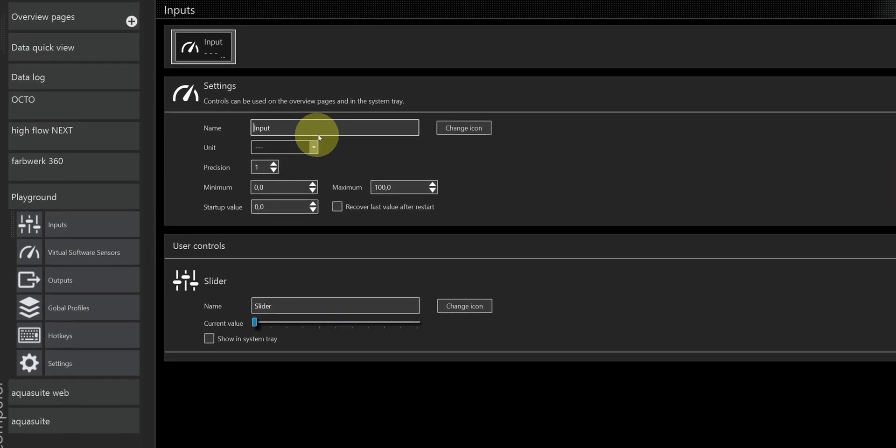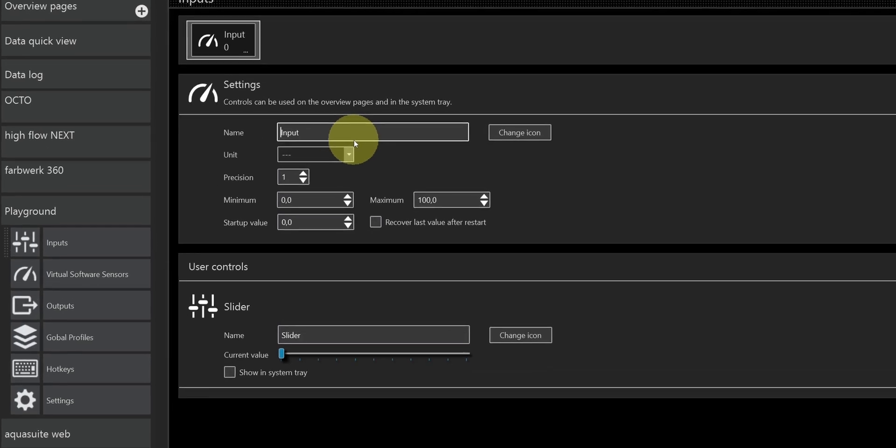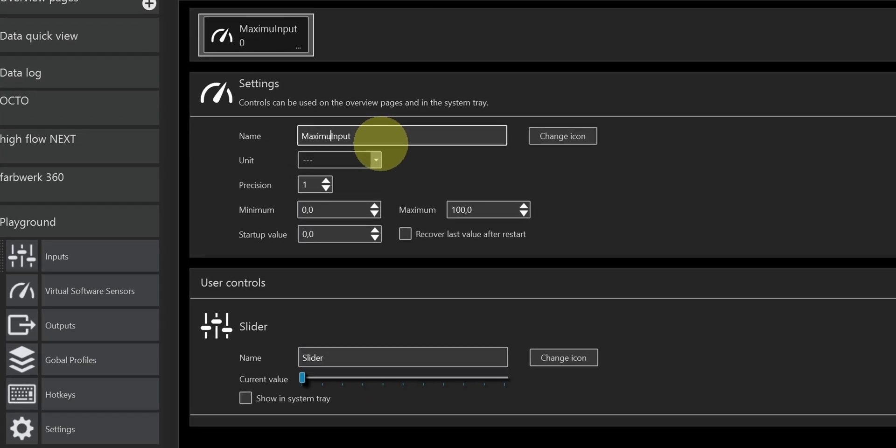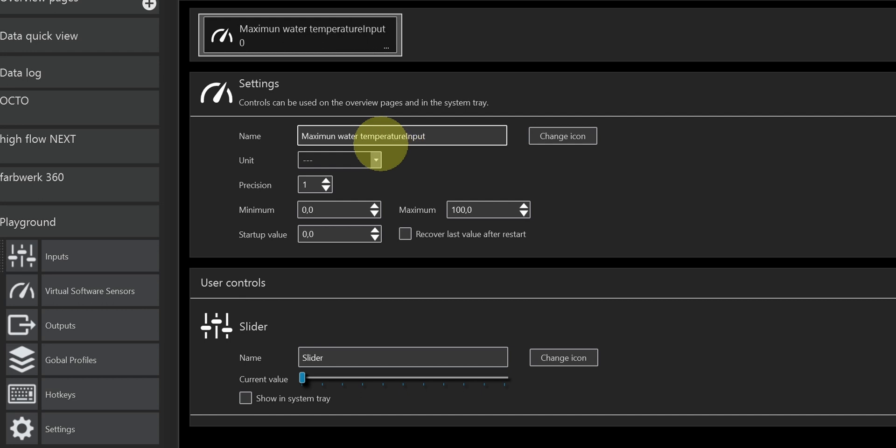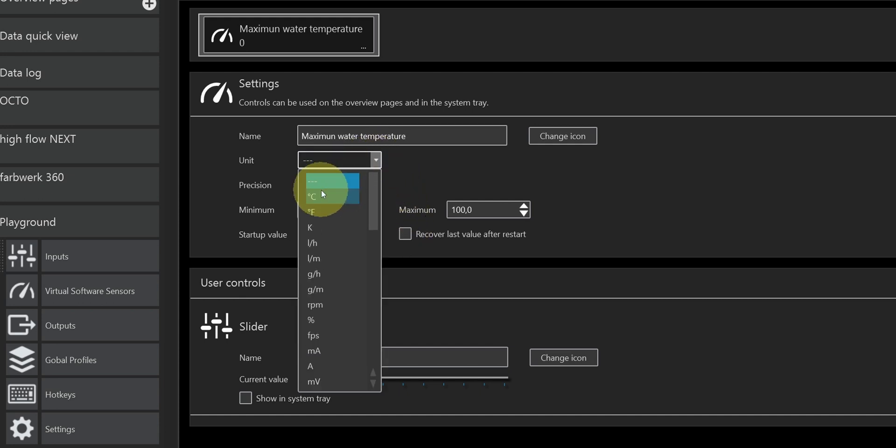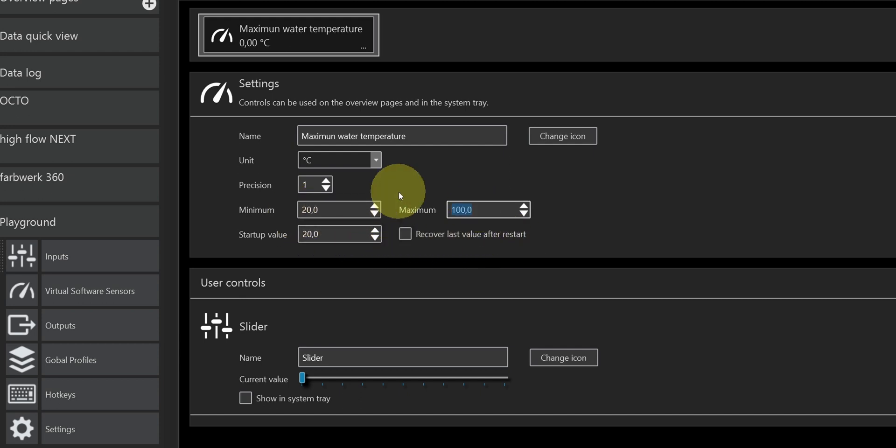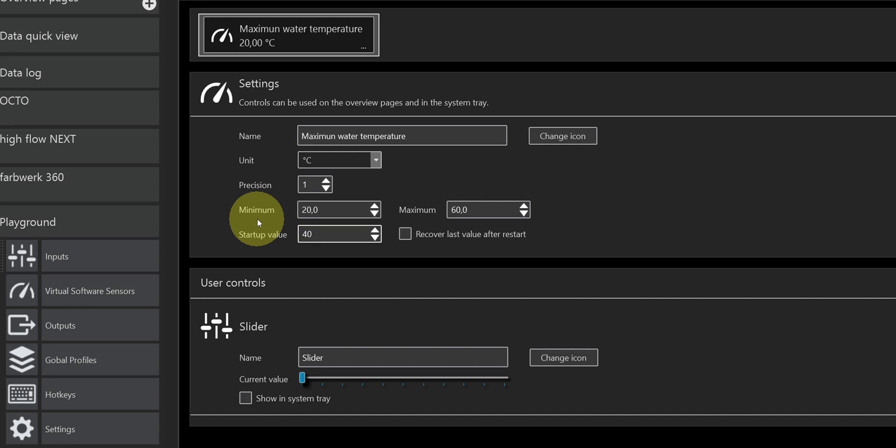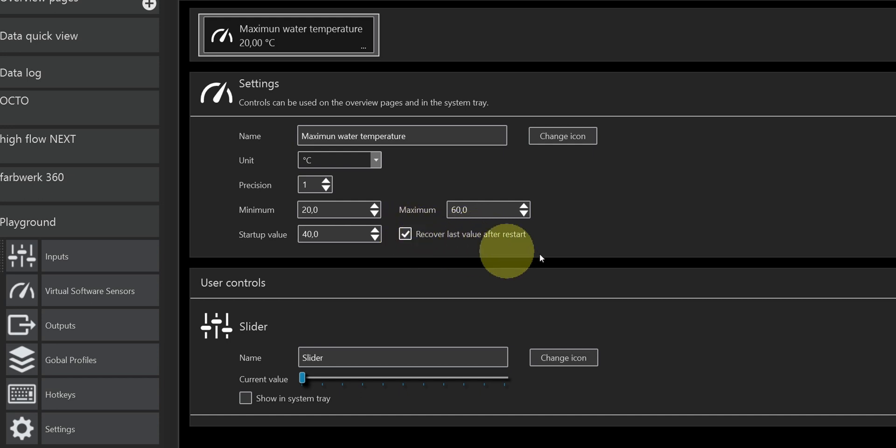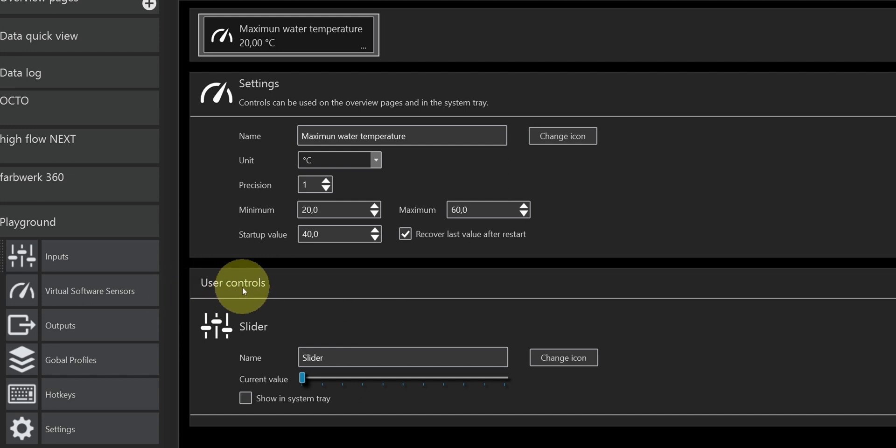I'll call it maximum water temperature. I'll set the unit to degrees Celsius and the precision to 1, so we get one decimal precision. I'll set the minimum temperature to 20 degrees and the maximum to 60. The startup I'll set to 40, since that's what I've been using on my controller until now. I'll put a checkmark in the recover last value after restart, otherwise the value would be reset to the startup value when my computer restarts.